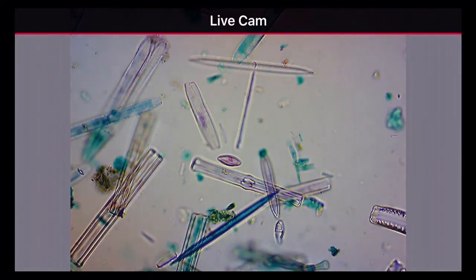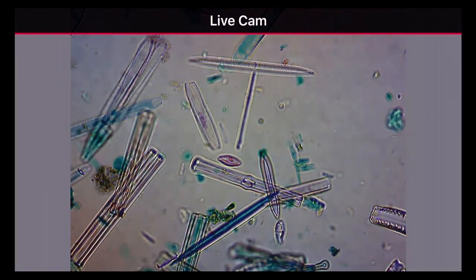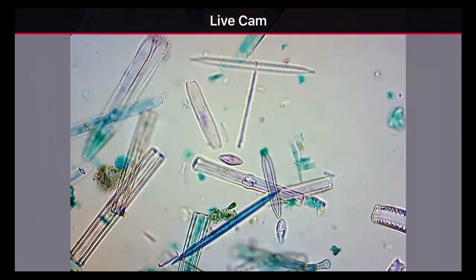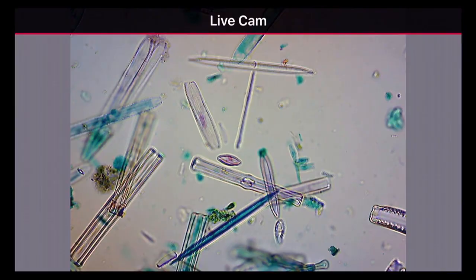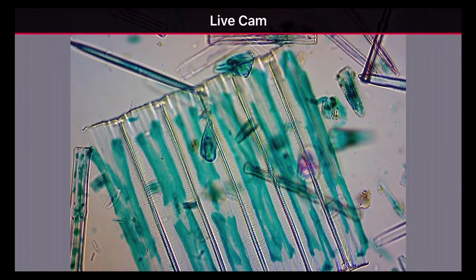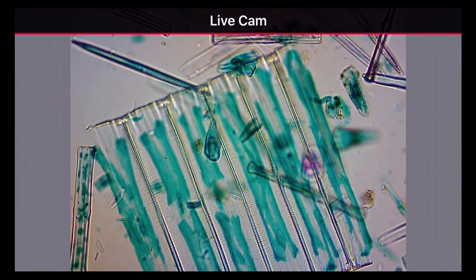So underneath the stage you have the diaphragm lens, and if you dial it to the left, you increase your light. If you dial it to the right, you decrease your light, increase the focus. You can see that your image changes quite a lot by using that method. So again, you always want to have the best possible image when you do your microscopy. Alright, let's look at one more slide.